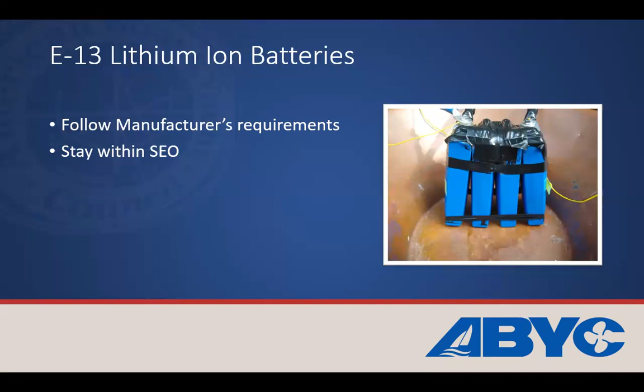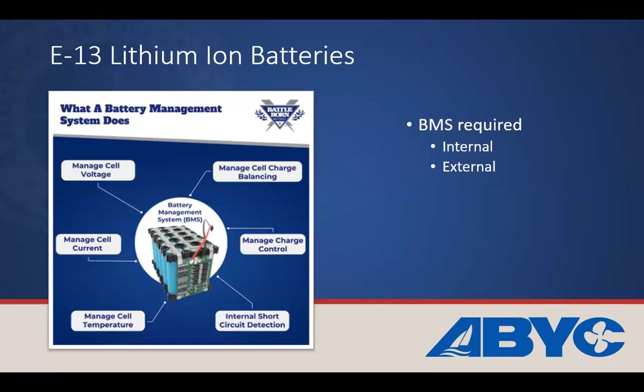What there is to make sure all this stays within the SEO is a BMS, a battery management system. It's looking at the battery, assessing its condition to try to keep it in a safe envelope. It's really the brains, and this is something that the ABYC E13 requires, a BMS. The BMS could be internal to the battery, and you see that in what we call drop-in batteries, it's built right into it. Or in bigger systems it may be external, hanging on a cabinet somewhere, with its own brain as you have multiple batteries. The most important thing is that you don't bypass the BMS, because that is what's trying to keep the battery in that safe state.